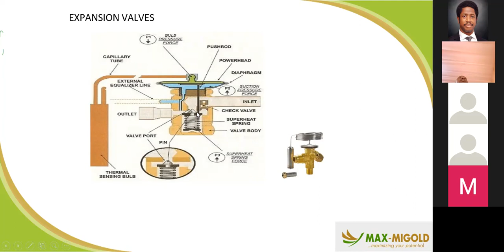Those that cannot afford it will braze ordinarily and just blow out the dust that is inside the copper. Because if copper dust accumulates inside and you seal it up, definitely it will find its way into this point and start blocking things around the system. And if there's a blockage, there's no forward movement, and the AC will definitely shut down. So these are the problems associated with it and the possible solutions.